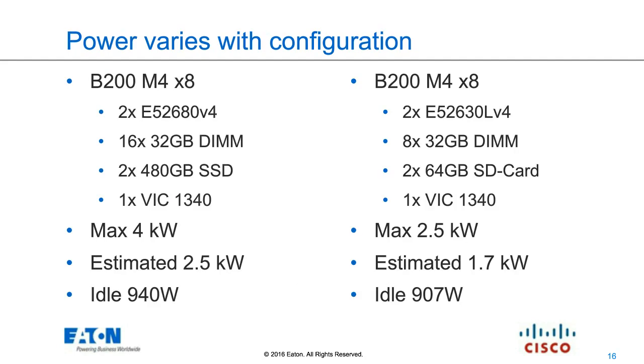Important thing to realize: power varies massively with configuration. I've run up two configurations through our power calculator here, a single blade chassis. I just swapped out the 2680s for 2630Ls, a low power processor, went from 16 DIMMs down to 8 DIMMs, and pulled the SSDs out and booted from SD cards. My power at max went from 4 kilowatts down to 2.5 kilowatts.